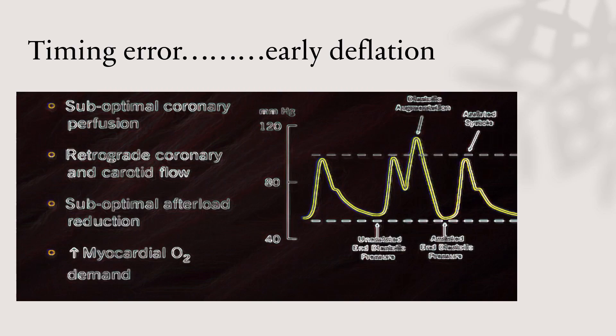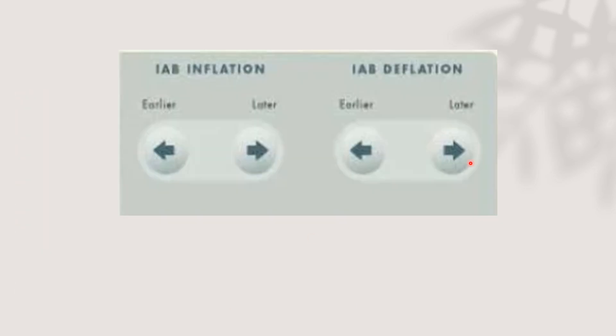As we mentioned before, the coronary arteries are perfused during inflation of the balloon, so early deflation will lead to suboptimal coronary perfusion and may lead to retrograde coronary and carotid flow that leads to angina pain. It can also lead to suboptimal afterload reduction, and all of this increases myocardial oxygen demand. To solve this issue, we will make the deflation slightly later on the console, and this can be judged through the arterial waveform on the console.